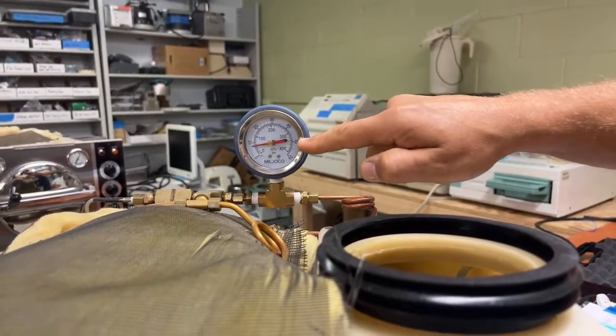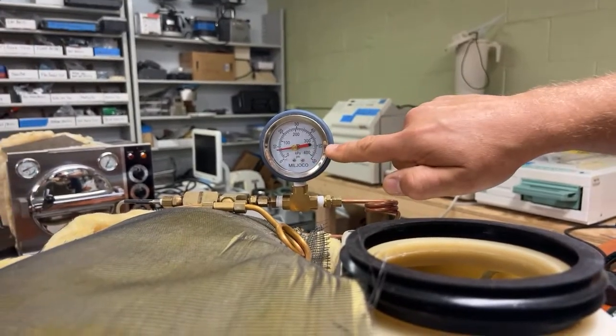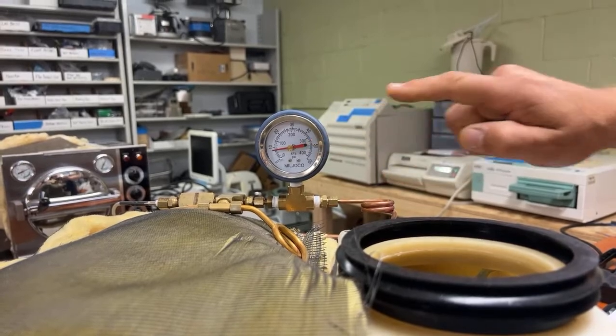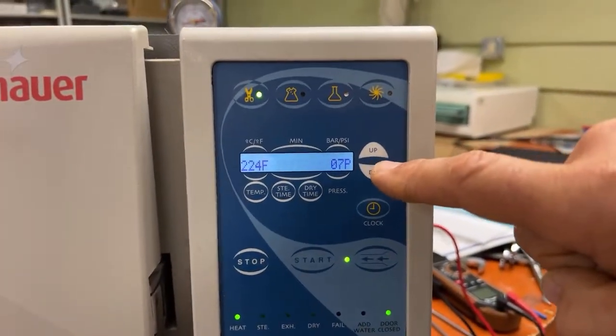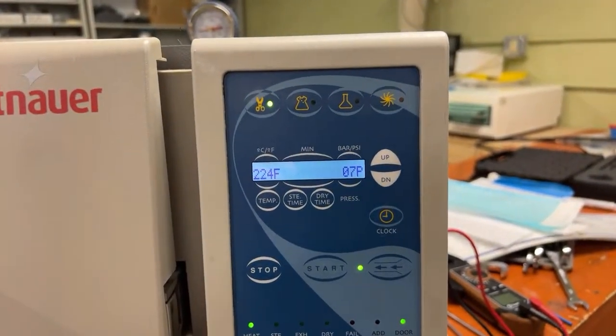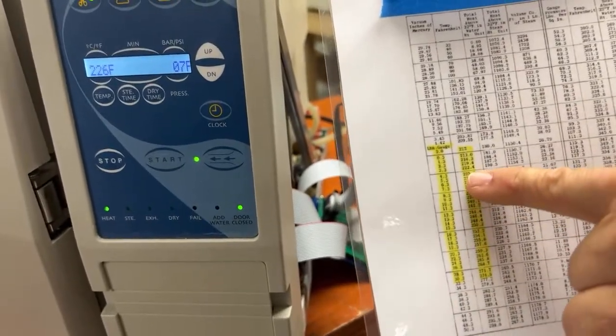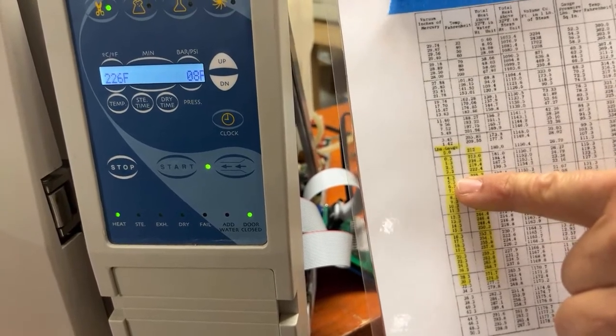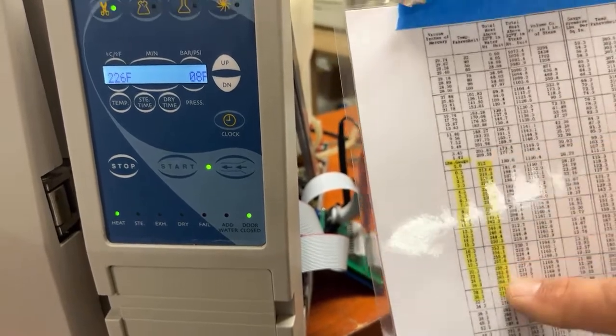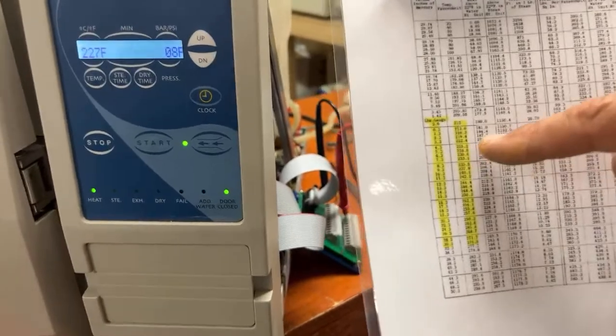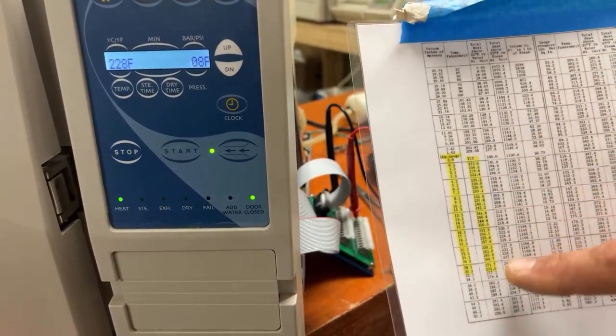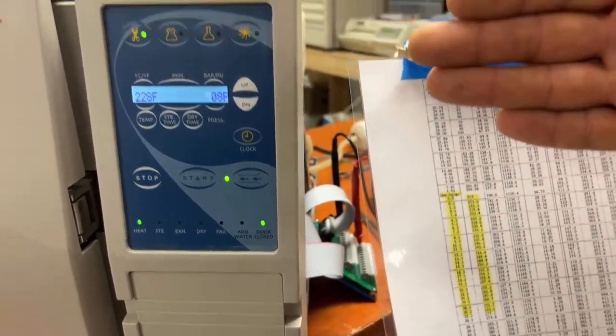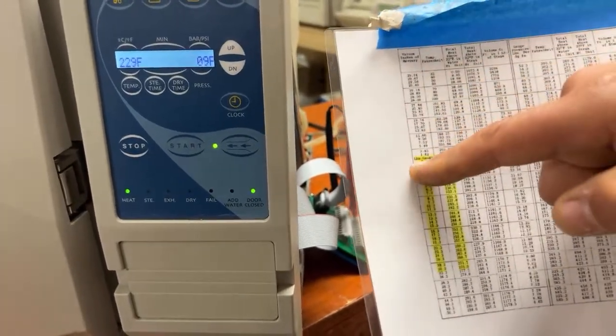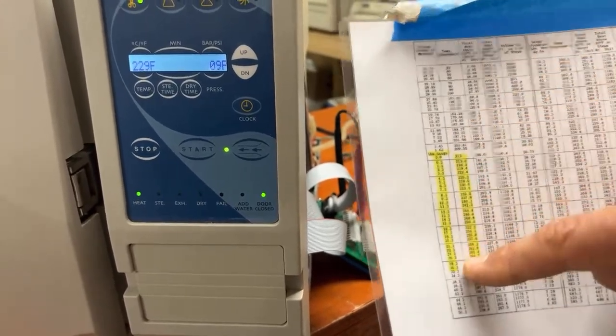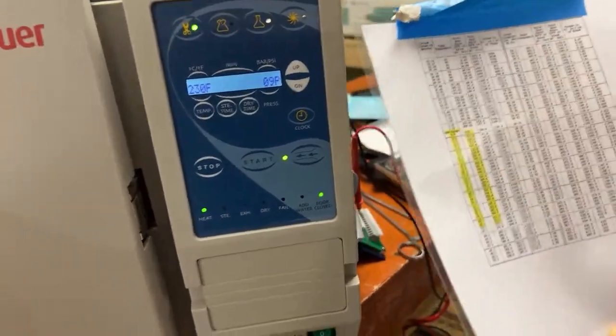Now we can start to compare this reading. Right now we're looking at about 8, climbing up to 9 psi. We can look here and see what our pounds are. Right now we're at about 7, so we're maybe a little bit low. We can look at this while we're doing it. 225 should be about 4.3 pounds. I wouldn't freak out in the middle, because obviously this is science and this is accurate, but these are not the critical values. The critical values are obviously 0, making sure that that's good, and then also the sterilization temperatures, which are going to be between 250 and 270 degrees.